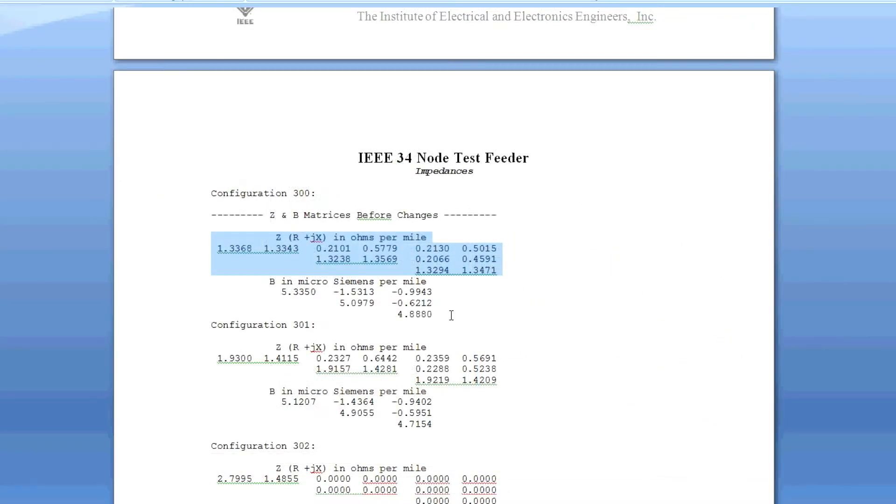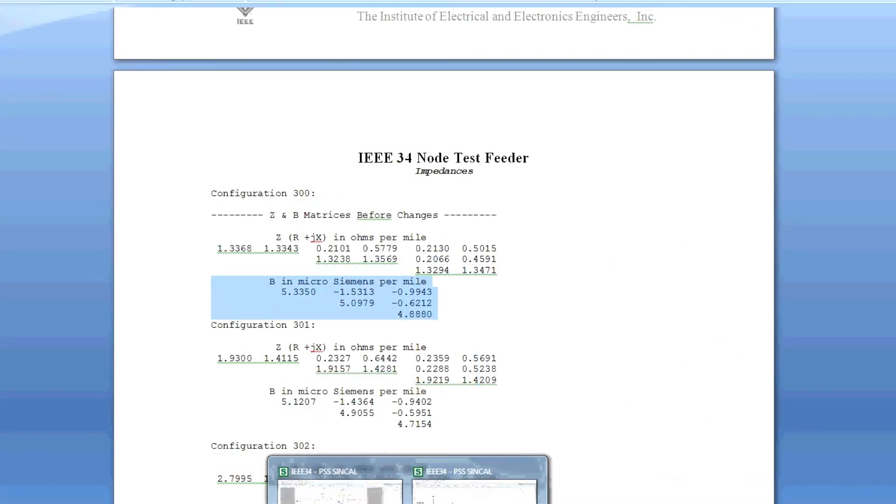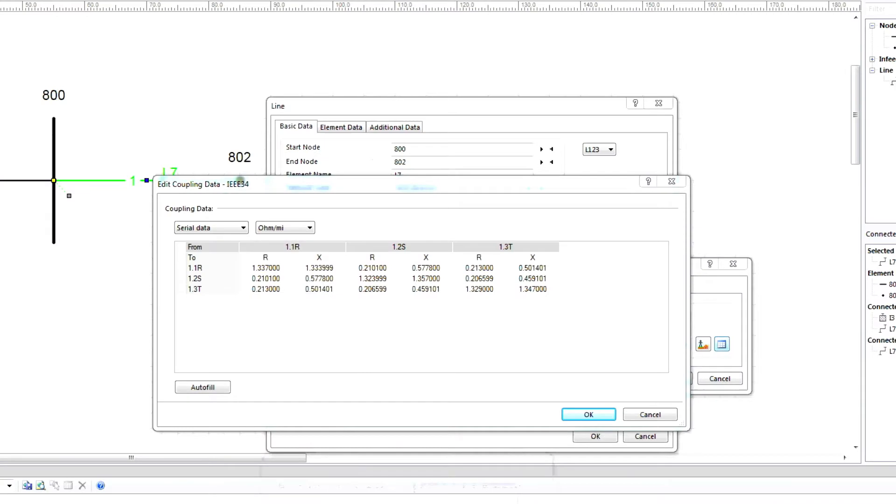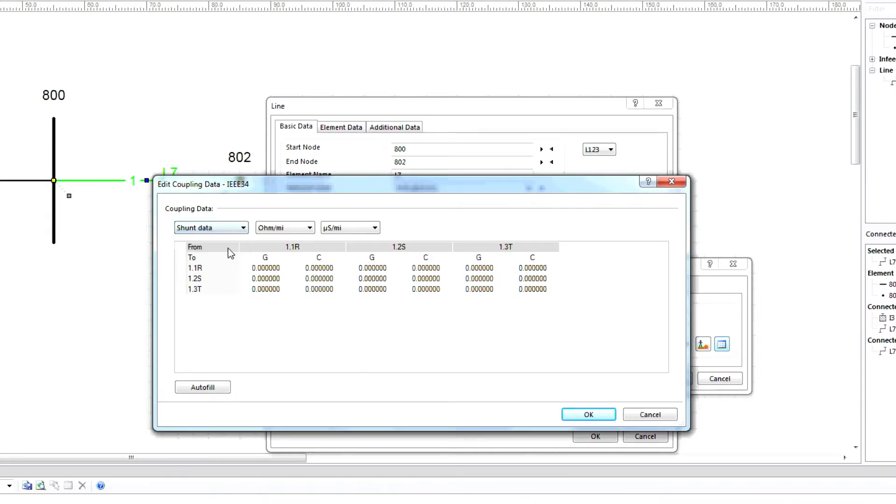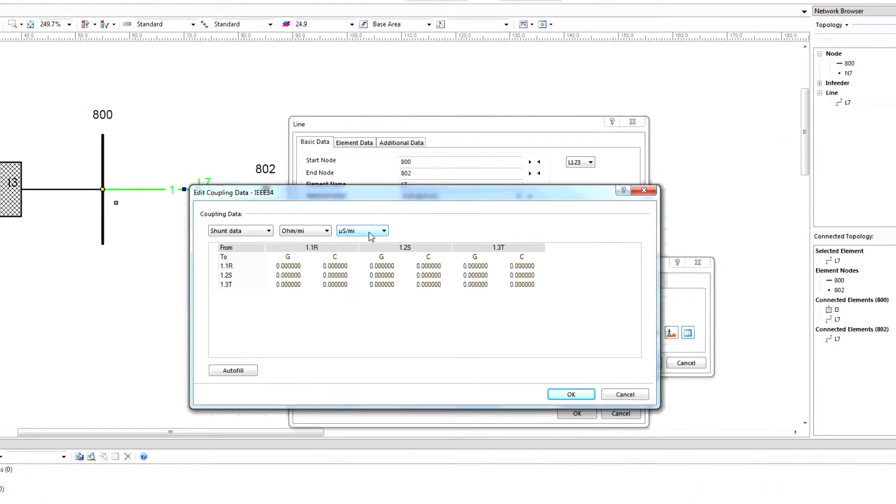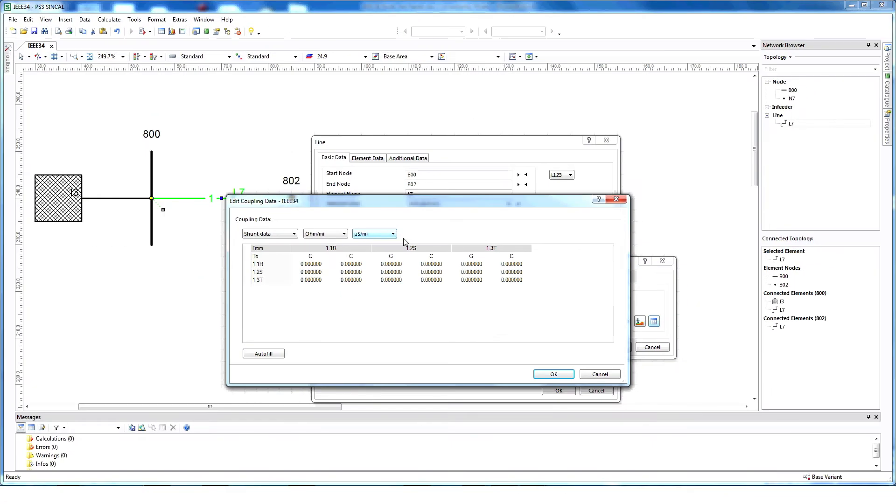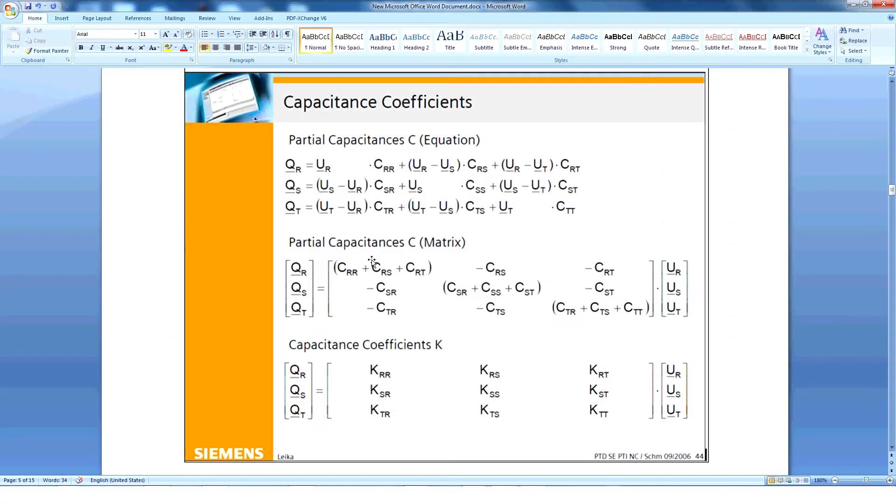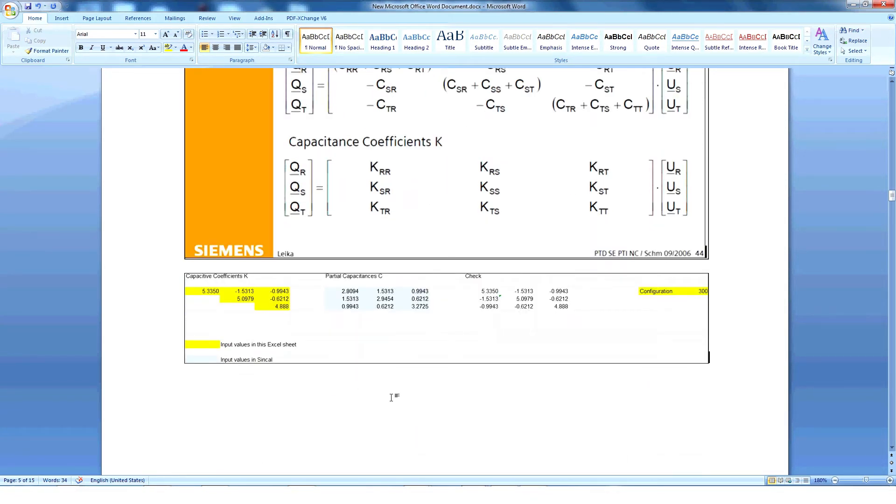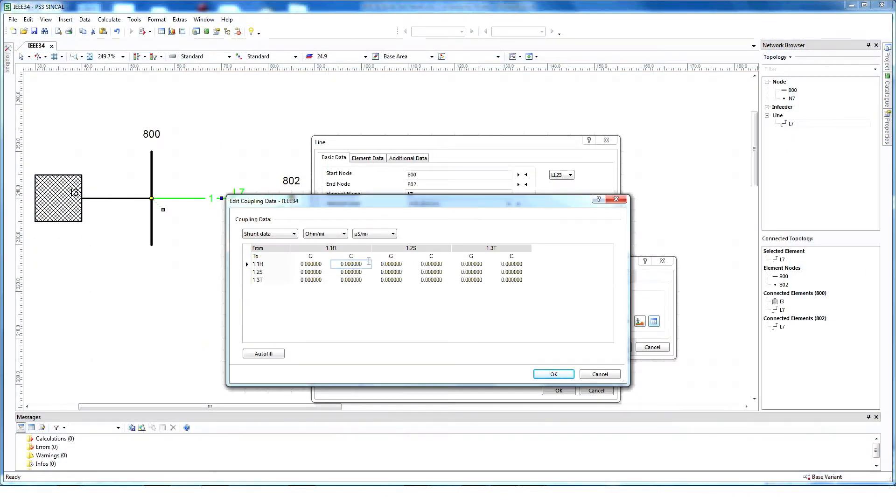Now provide the shunt data information in PSS SINCAL. Click on shunt data. Select this option for the shunt data unit and then provide IEEE shunt data. Please note, SINCAL expects the values of the shunt capacitances as partial capacitances, so conversion may be needed. Enter the shunt data into the table and then click OK.